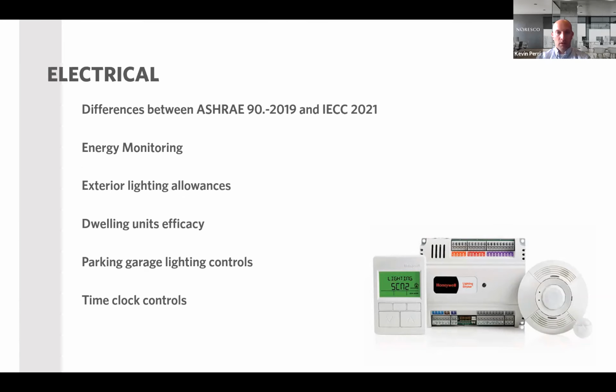The differences are energy monitoring. I'm trying to find my notes here. Okay, so in IECC, energy monitoring is required on spaces over 25,000 square feet. And you have to measure, monitor, record, and report that energy, and it's broken down into categories: HVAC, interior lighting, exterior lighting, plug load, process load, and building operations and other miscellaneous loads. So there's 5 categories that IECC requires you to monitor from an energy standpoint.